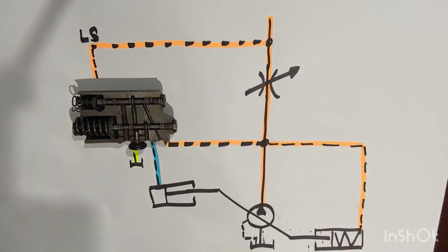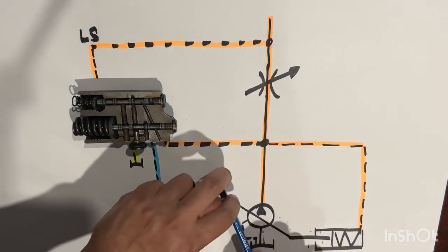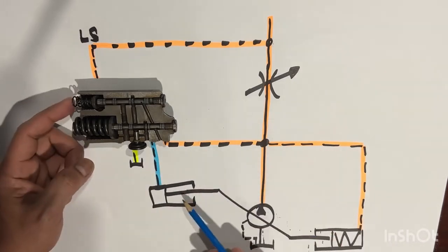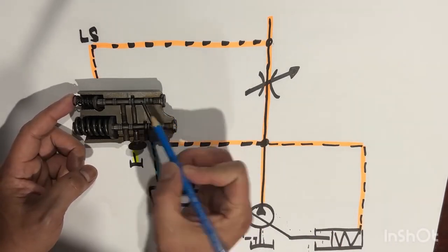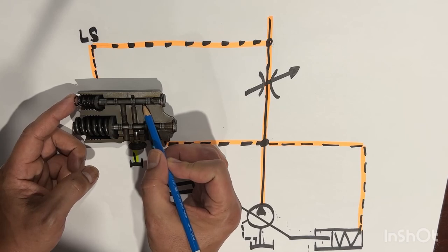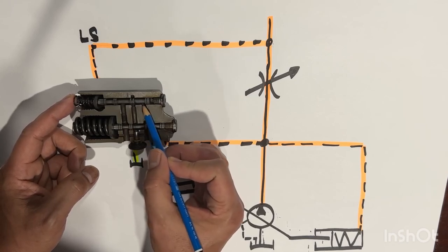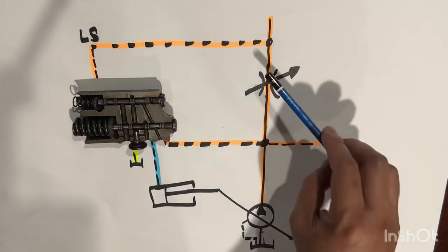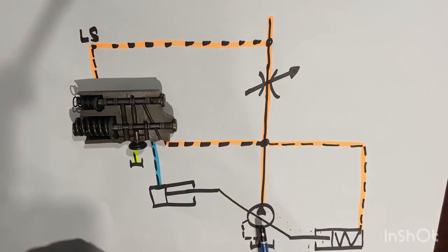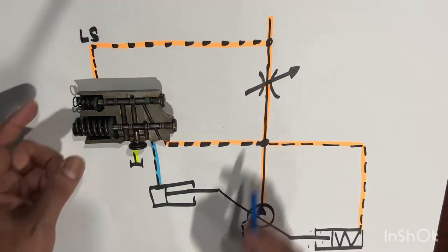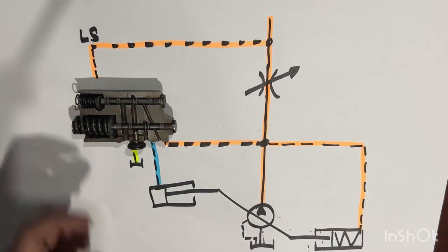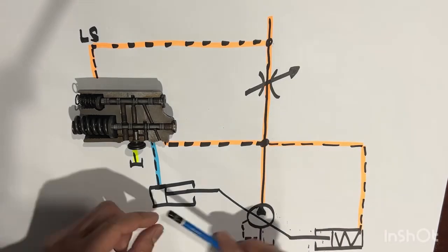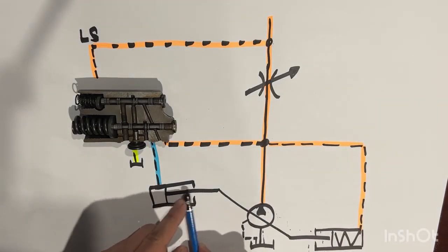So when the Q is enough to maintain the delta P of 15 bar, then the de-stroking will stop because the delta P is balanced already. It maintained the delta P already. So this spool here will maintain like that. Now the pump flow is at 50% because the demand is only 50%. The pump flow rate is displacing what the demand is. When the delta P is not yet reached, this will continue moving to de-stroke to the minimum position.